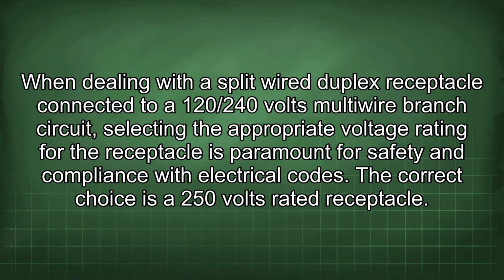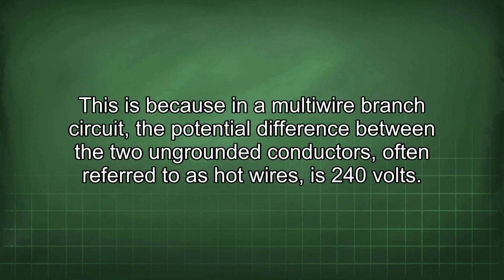When dealing with a split-wire duplex receptacle connected to a 120/240 volts multi-wire branch circuit, selecting the appropriate voltage rating for the receptacle is paramount for safety and compliance with electrical codes. The correct choice is a 250 volts rated receptacle. This is because in a multi-wire branch circuit, the potential difference between the two ungrounded conductors, often referred to as hot wires, is 240 volts.